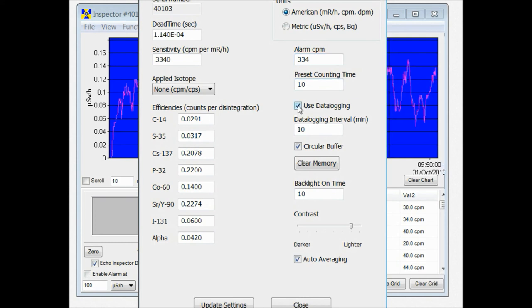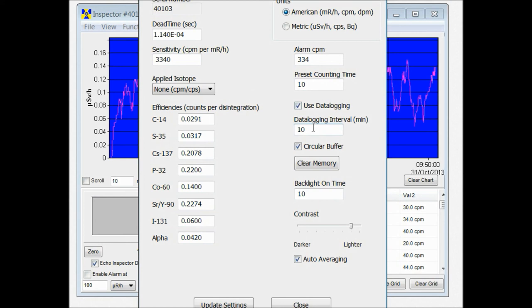This is a way to turn on the data logging that's a little bit easier than the utility menu on the unit itself. And you can also set the data logging interval. Right now it's set at a default of 10 minutes.